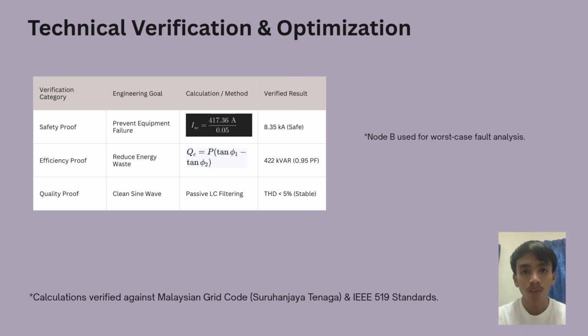First, for safety, we dive into the engineering verification. We calculate a worst-case fault current of 8.35 kA based on our full load current of 417.36 amperes. To ensure the absolute safety of the facility, we have specified circuit breakers with a 36 kA breaking capacity. This provides an excellent safety margin for our infrastructure. Next, for efficiency, we address the power factor. By installing a 422 kVAR capacitor bank, we improve the system efficiency from 0.8 to a high 0.95 power factor.